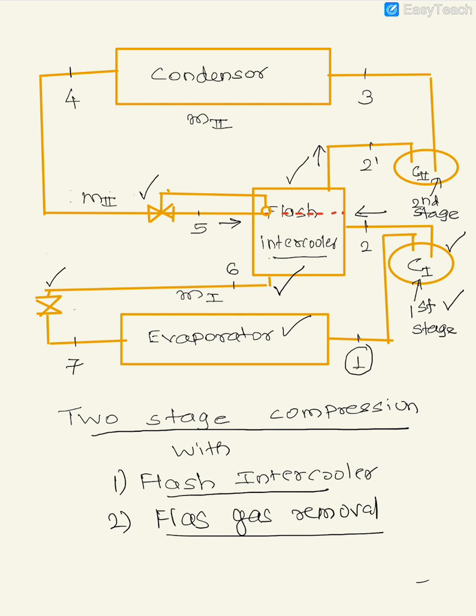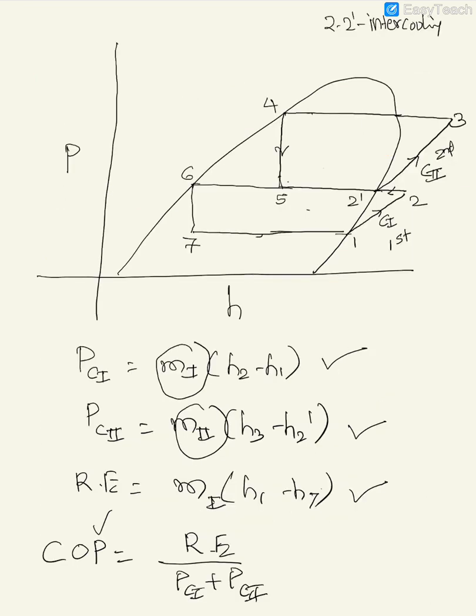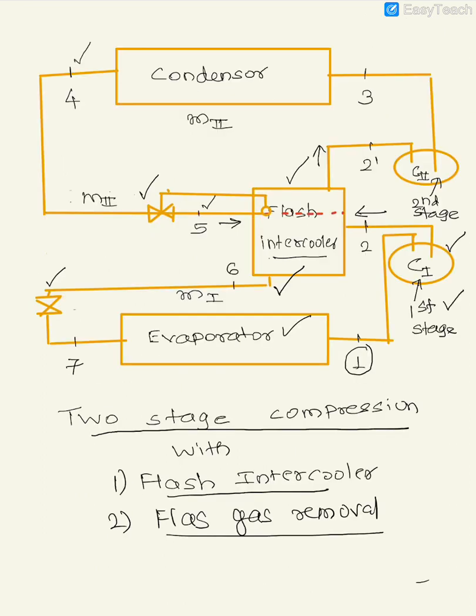You need to be very clear as to how this flash intercooler helps in flash gas removal. Look at state 4 to 5 — this is an expansion in a throttling device, and at state 5, flash gases are generated. These flash gases do not play any role in the refrigerating effect, and it is good that they are removed. This removal is achieved by making use of the flash intercooler.